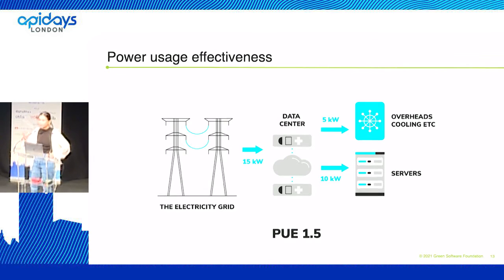If our data center's PUE is 1, what that means is for every kilowatt hour of electricity that comes in, it all goes to the servers. But when PUE increases to 2, that means for every 2 kilowatt hours of energy that comes in, one goes to do something useful in our server, and the other has to go to overhead activities supporting the data center. Another way we can think of PUE is as a multiplier of an application's energy consumption.